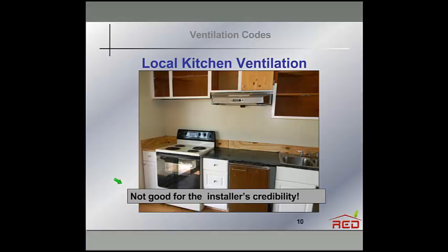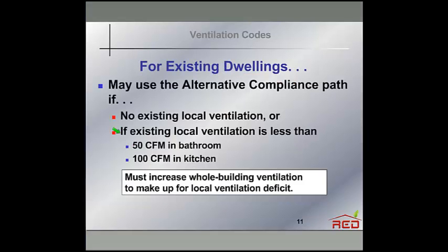I can't hear you laughing, unfortunately, but this is interesting. This is funny. This is a really big screw up. You really have got to wonder how this ever happened. But I want to make sure that you understand that this does comply with the ASHRAE standard. The capture efficiency of this particular range hood is going to be very low, but it does comply with the standard.